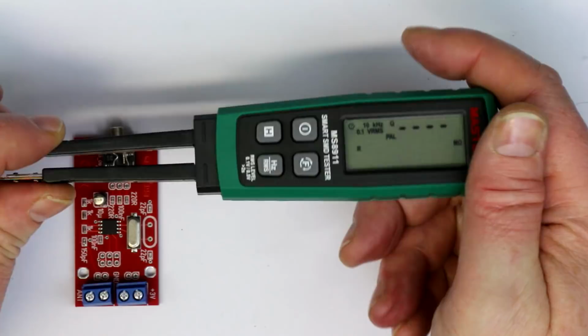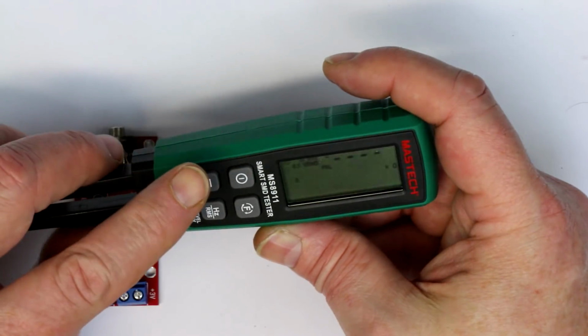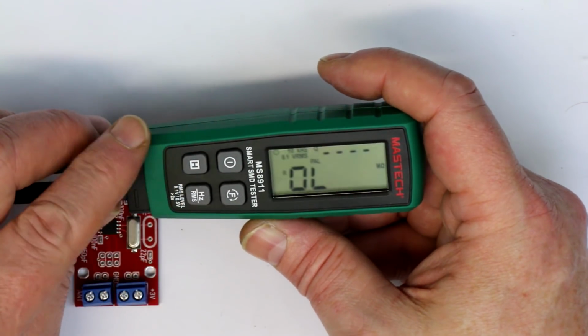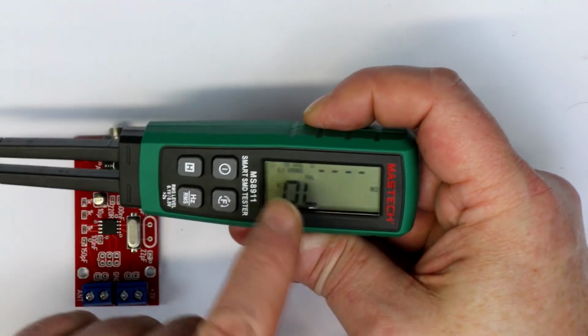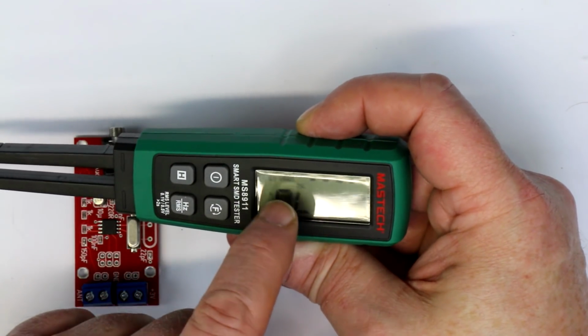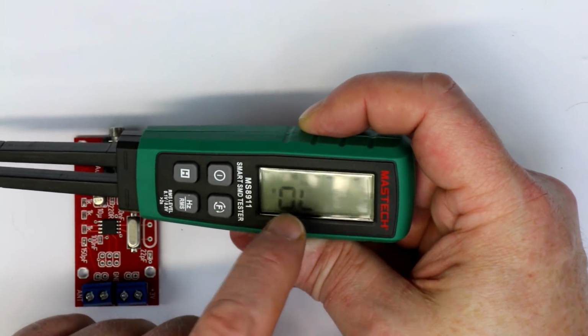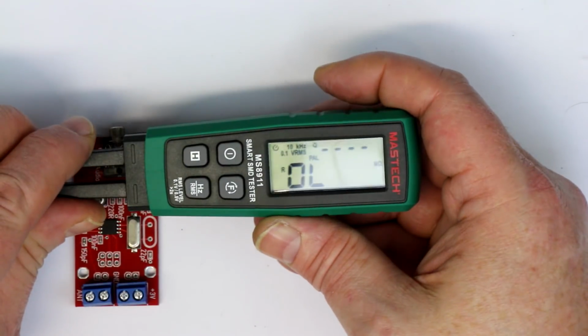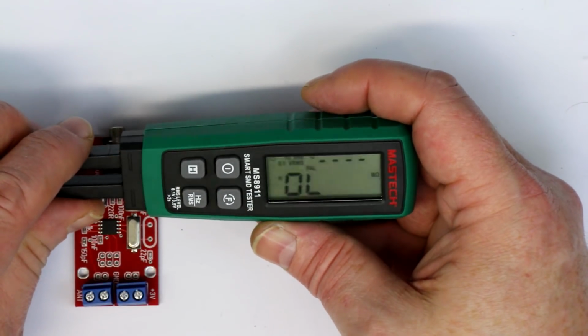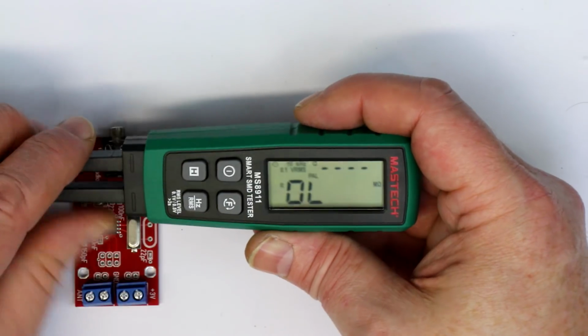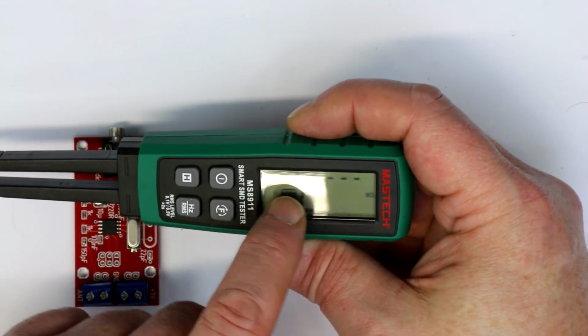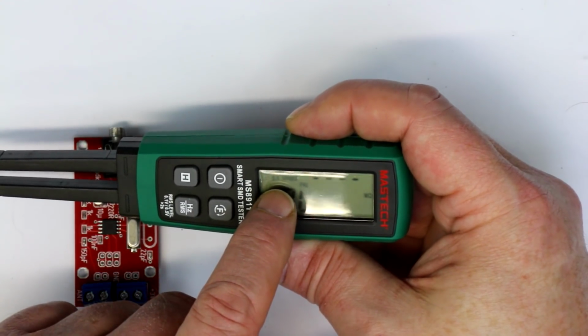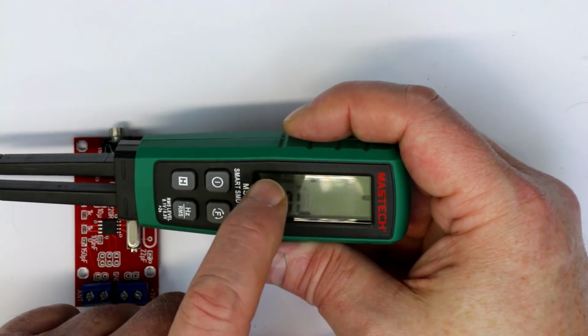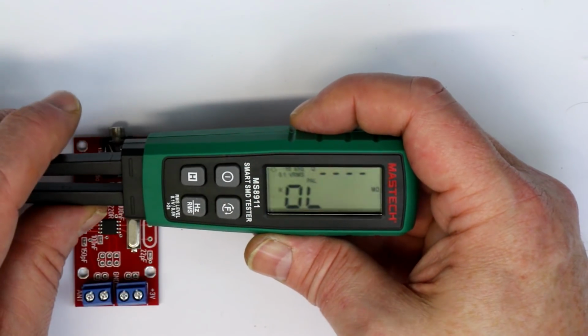Another thing I noticed: when it goes into auto power off, it forgets the last setting of frequency and measurement voltage. It would have been nice if it could store the last set frequency and voltage, because most often you'll use the combination of 0.1 volts RMS measurement voltage and 10 kilohertz measurement frequency.